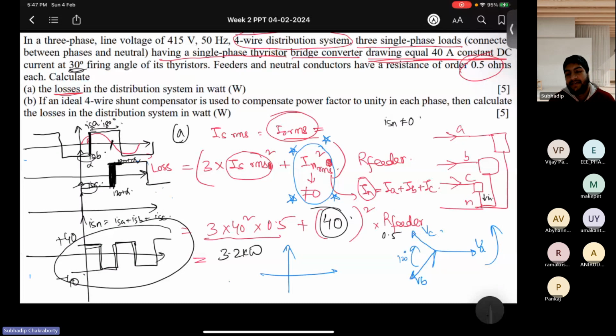So just the part A I have designed specially to make you realize that, like the sinusoidal case, if you have linear loads... these are not linear loads, these are non-linear loads, drawing non-linear currents from the supply. So in such cases, even if they are symmetric loads, this problem was designed just to make you realize that the neutral current still is not 0 and it is causing additional loss. So that's why we are improving the power quality as well as providing load balancing, which you have learned in the week 2 also. So this is the main condition, that it is leading to additional losses.